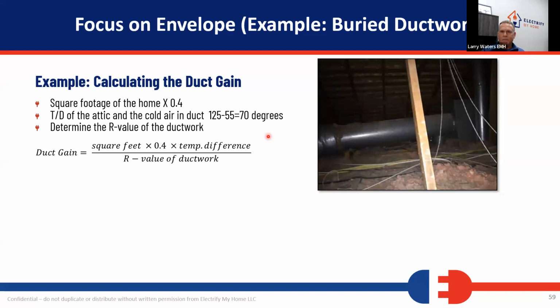that gives us our total internal duct surface area. We take the temperature difference of the attic and the air going through the duct. And if we have our house set at 75, our air going through the ductwork should be around 55. If the system is pulling in 75-degree air and it's operating properly, it should be giving you 55-degree air out. When that 55-degree air blows into hot ductwork in the attic, the ductwork sucks a lot of the cooling energy out of it, and it often delivers air that's much warmer on the other end, and that's what this is figuring out. So if we just look at, and you guys in the solar business running wires through attics, you know it gets a lot warmer than 125.